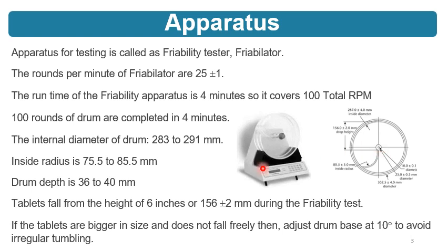The tablets fall from a height of 6 inches. So in an interview it may be asked what is the height from which the tablet falls onto the lower surface in the friability testing. So 6 inches or 156 mm is the height. So this drum will rotate like this, and from here the tablets will fall down.